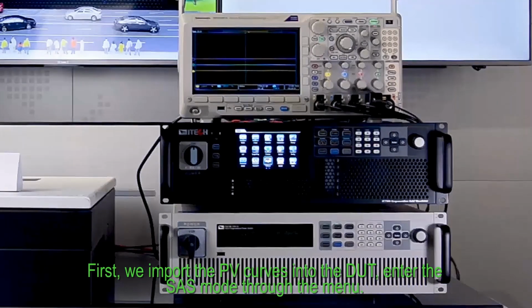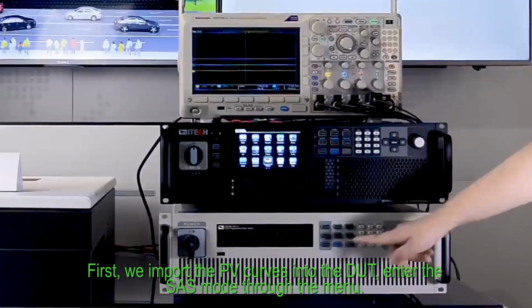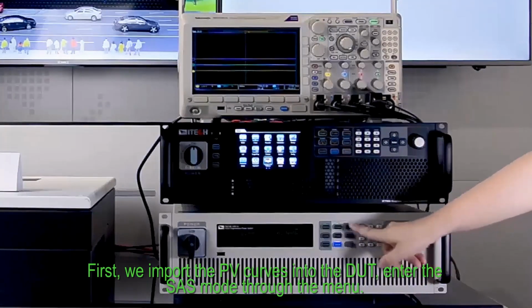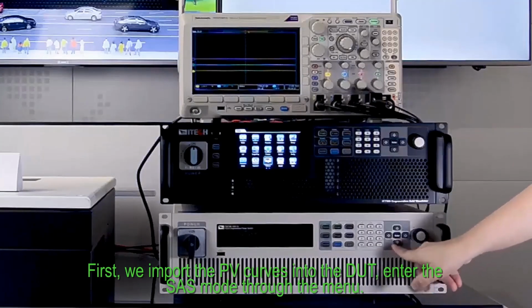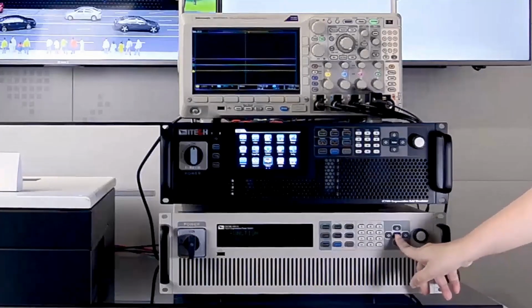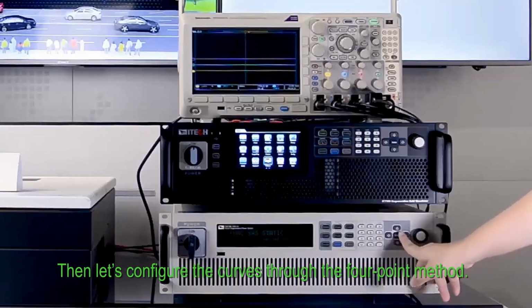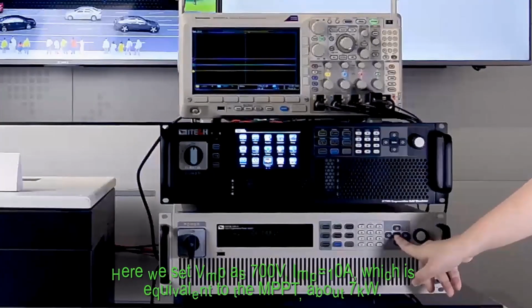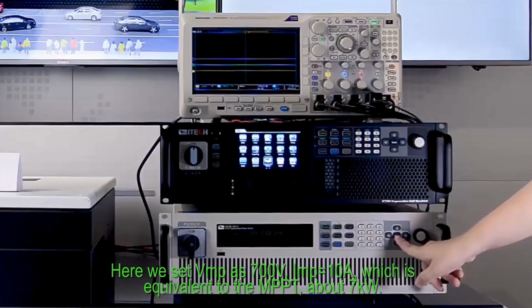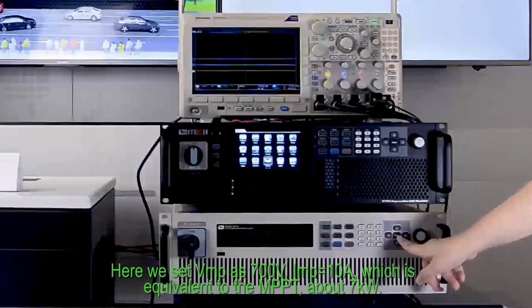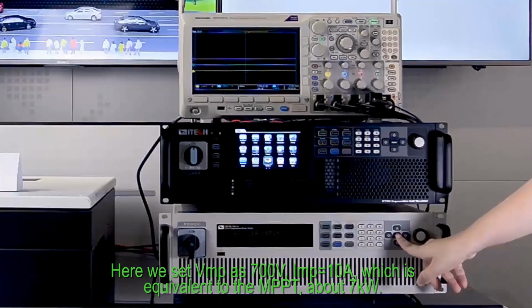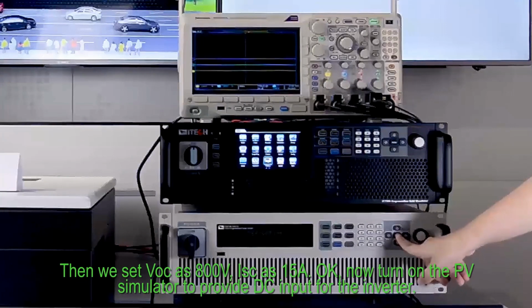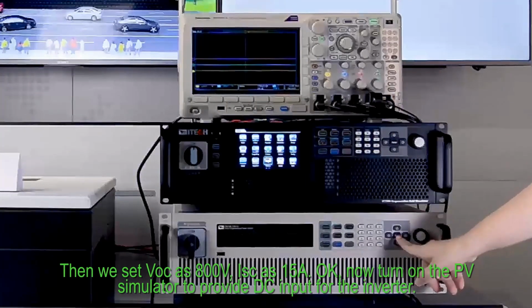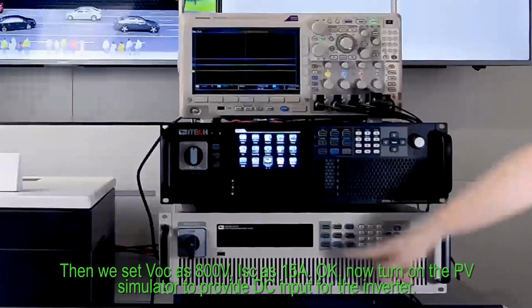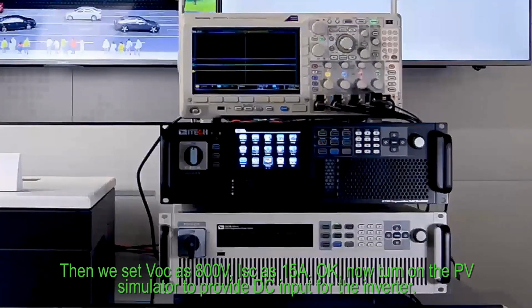First, we import the PV curves into the DUT, entering the SAS mode through the menu. Then let us configure the curves through the 4-point method. Here we set VMP as 700V, IMP equals 10A, which is equivalent to the MPPT, about 7 kilowatts. Then we set VOC as 800V, ISC as 15A. OK, now turn on the PV simulator to provide DC input for the inverter.